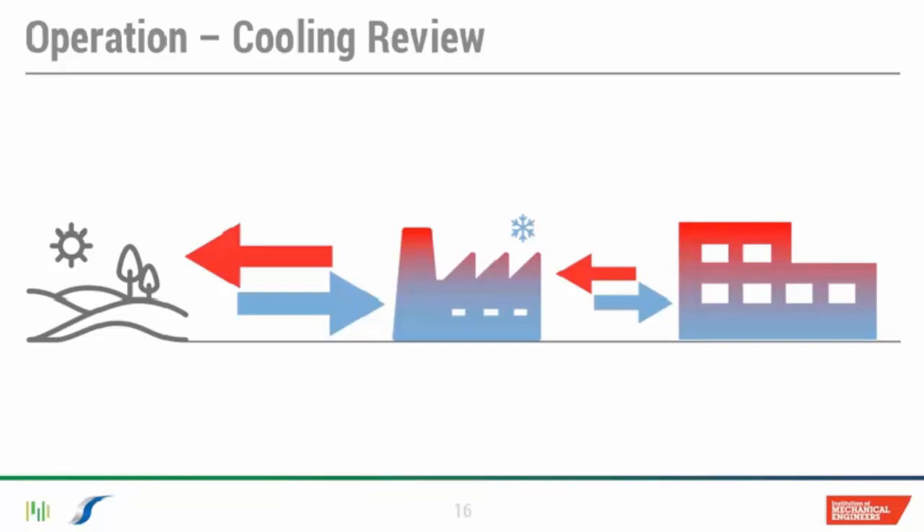To ensure we deliver air at those temperatures and allow free cooling opportunities, we need to make sure that heat picked up across the IT equipment stays contained until it's rejected outside into the atmosphere. We do that by having either hot aisle containment or cold aisle containment. Best practice is hot aisle containment — we contain all the hot air exhaust from the IT equipment, pass it back to the cooling equipment externally, and before it's recycled into the data hall it's cooled back down to 24 degrees. At 40 megawatts across the campus, we have capacity for about 7,000 IT racks, and the Cambridge One supercomputer takes about 70 of those cabinets — so that 40 megawatts could power around 100 supercomputers.